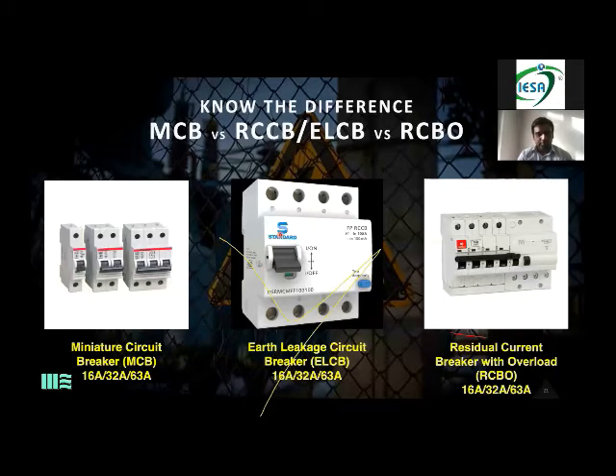ELCB, on the other hand, does one function, which is earth leakage, the earth leakage circuit breaker. We've spoken about how earthing is such an important point in an exhibition or outdoor event, and everything can go wrong if the earthing is not right. As soon as you start using an ELCB, it will save you from earth leakage also. If there is any earth fault happening in the system, it will automatically trip. RCBO is a combination of MCB and ELCB. It does all three functions: short circuit, overload, and earth fault.